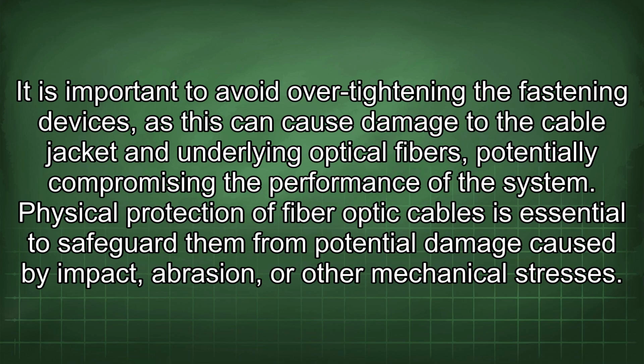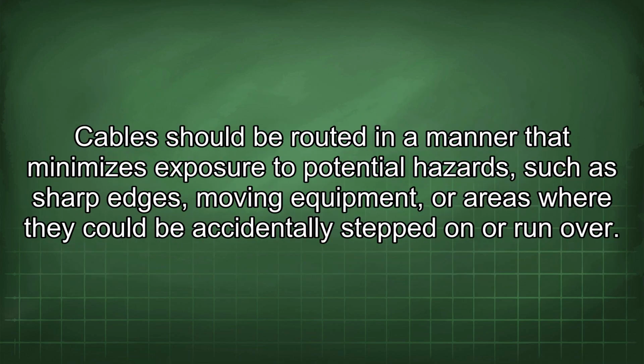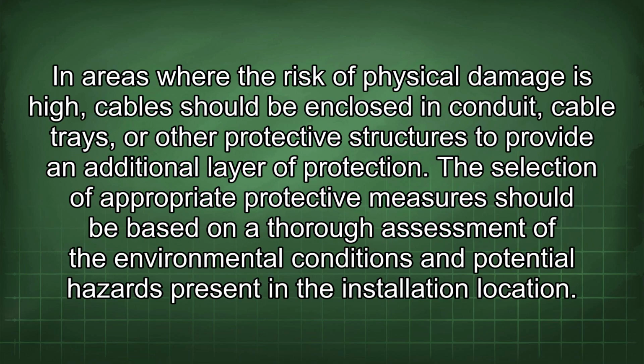Physical protection of fiber optic cables is essential to safeguard them from potential damage caused by impact, abrasion, or other mechanical stresses. Cables should be routed in a manner that minimizes exposure to potential hazards such as sharp edges, moving equipment, or areas where they could be accidentally stepped on or run over. In areas where the risk of physical damage is high, cables should be enclosed in conduit, cable trays, or other protective structures to provide an additional layer of protection. The selection of appropriate protective measures should be based on a thorough assessment of the environmental conditions and potential hazards present in the installation location.